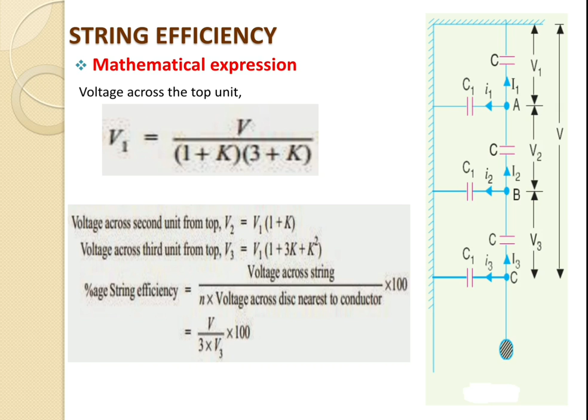Now we will go for the methods of improving string efficiency. There are a number of methods which can be used for improving the string efficiency. It is clear that the potential distribution in the string of a suspension insulator is not uniform because of the presence of shunt capacitance. The maximum voltage appears across the disc nearest to the conductor. If breakdown or flashover takes place in the disc nearer to the conductor, the breakdown of the other units will take place in all the discs. It is necessary to equalize the potential across the various units of the string, or to improve the string efficiency, and there are a number of methods which can be used.